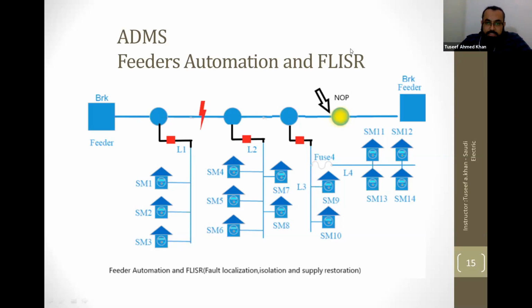If you put this option on auto, this fault current will go to the fault recorder and the readings will go to your ADMS software, which will calculate using the fault localization method. FLISR means fault localization, isolation, and supply restoration automatically. Your fault will be localized remotely and automatically using different power calculations and the rules you set in your ADMS software, and then it will decide.